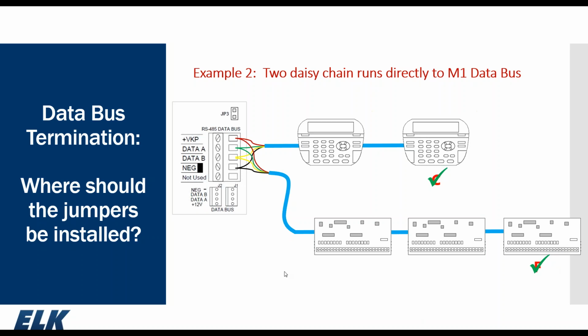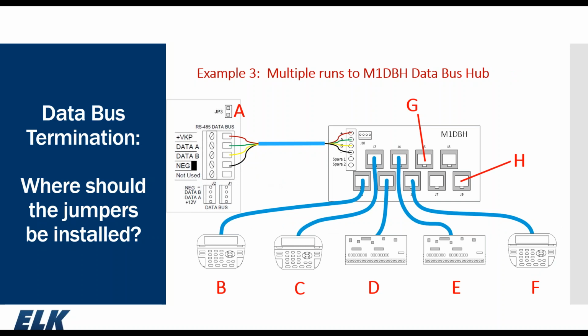And if we were to power down and measure the resistance across A and B here, we should read between 60 and 70 ohms as a good rule of thumb. If we're using our DBH hub, the M1 DBH, which uses the Cat5 or Cat6, we have 5 devices connected. They're connected in J1 through J5. So with the single DBH hub, we would make sure the panel is terminated, and then the RJ45 connector is installed in J6. If I added another device, I would move that terminating jumper to J7 and plug my new device into J6.